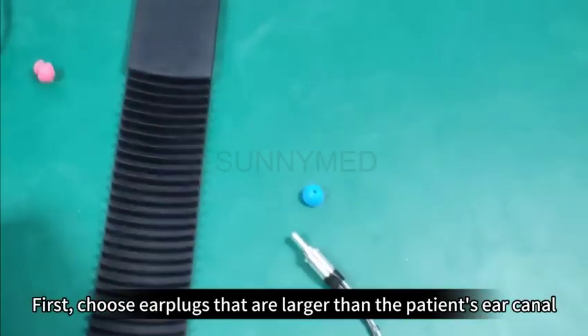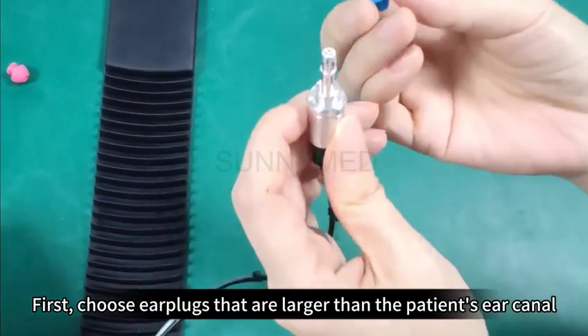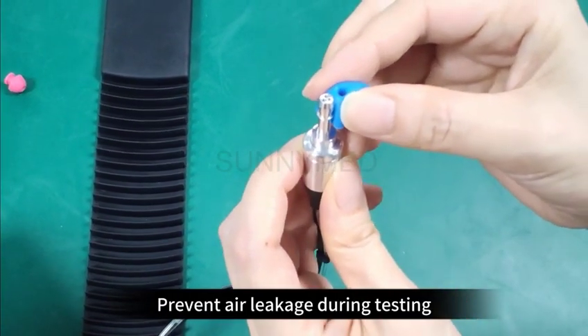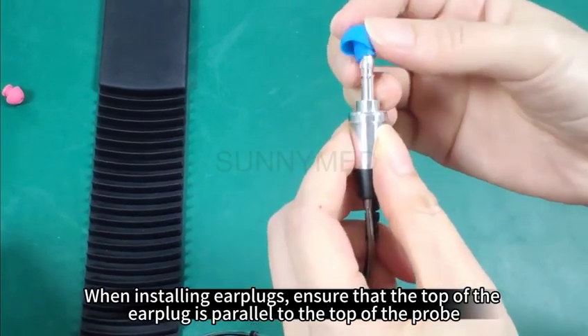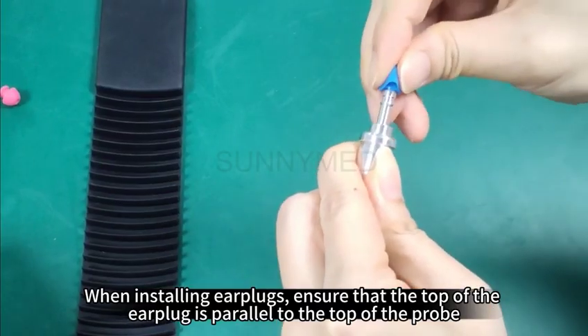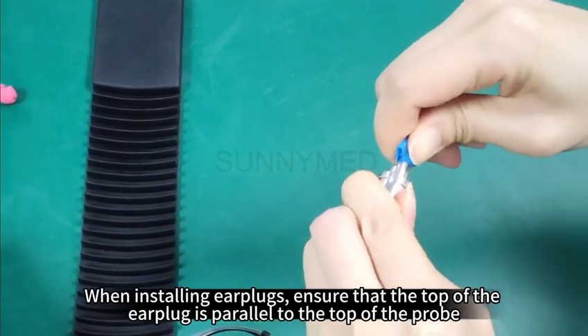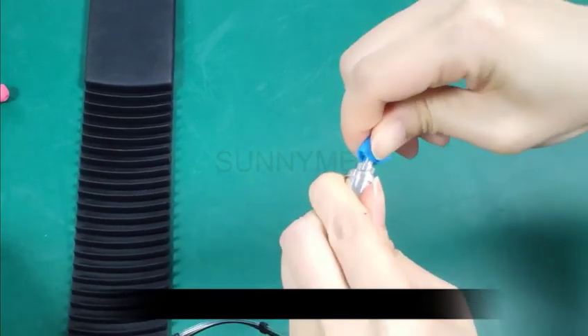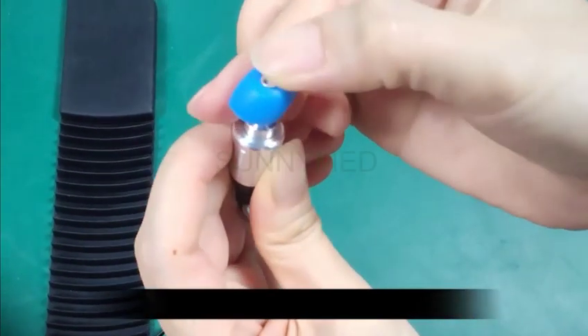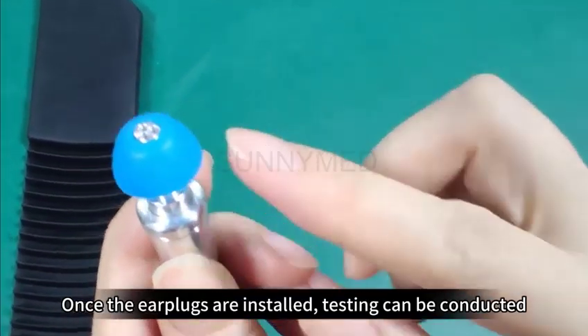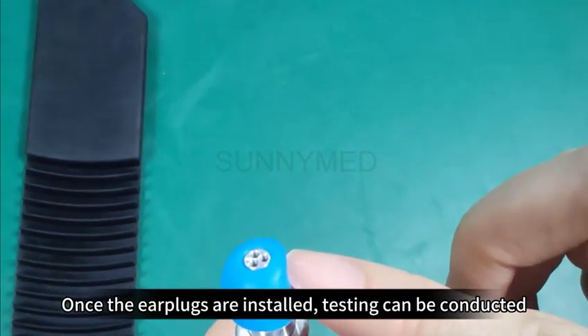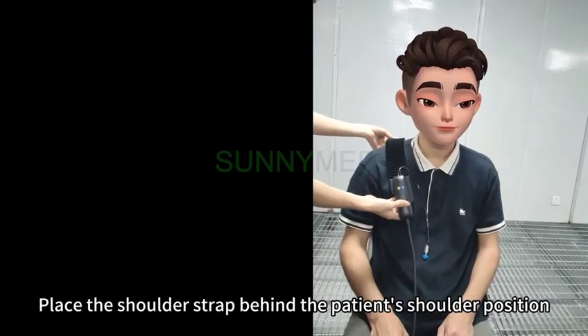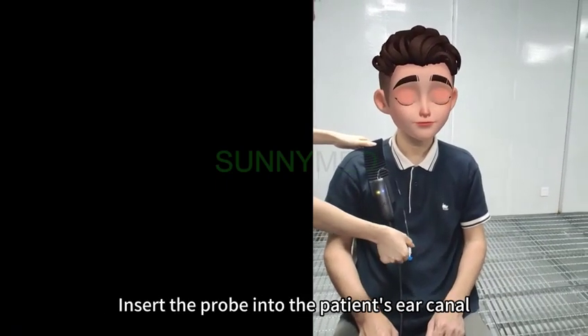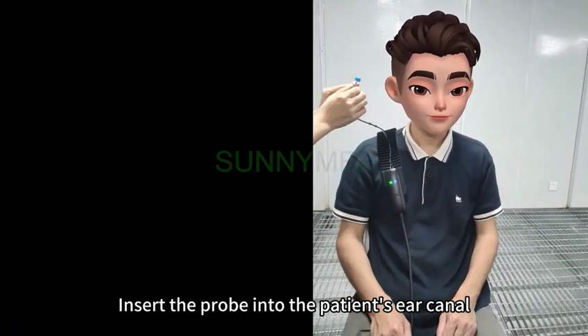First, choose earplugs that are larger than the patient's ear canal to prevent air leakage during testing. When installing earplugs, ensure that the top of the earplug is parallel to the top of the probe. Once the earplugs are installed, testing can be conducted. Place the shoulder strap behind the patient's shoulder position. Insert the probe into the patient's ear canal.